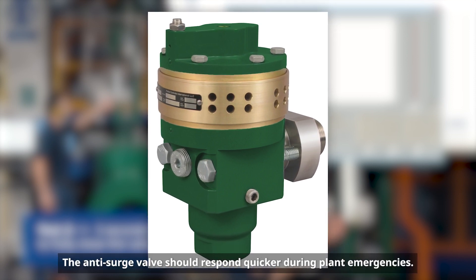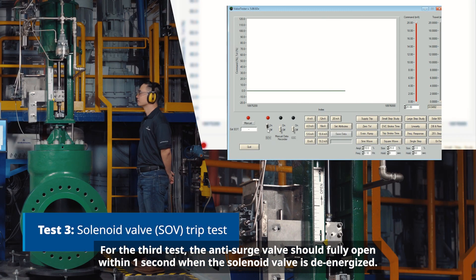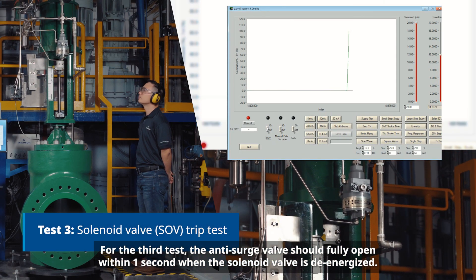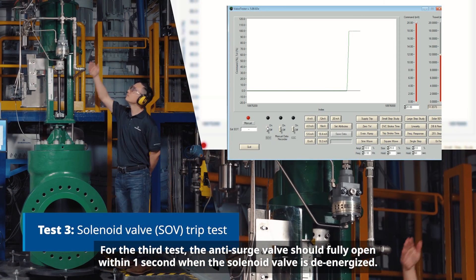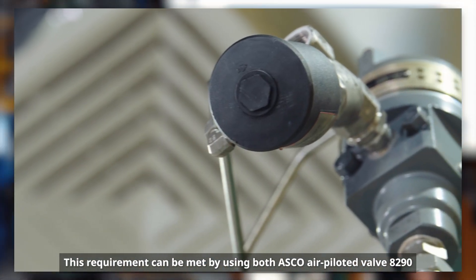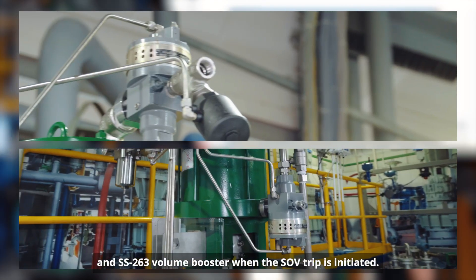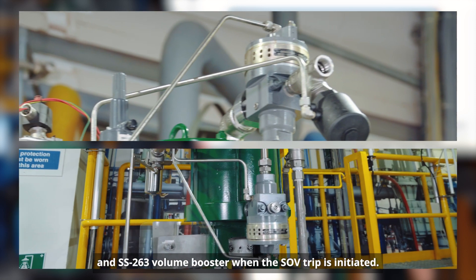The anti-surge valve should respond quicker during plant emergencies. For the third test, the anti-surge valve should fully open within one second when the solenoid valve is de-energized. This requirement can be met by using both the ASCO air-piloted valve 8290 and SS263 volume booster when the SOV trip is initiated.